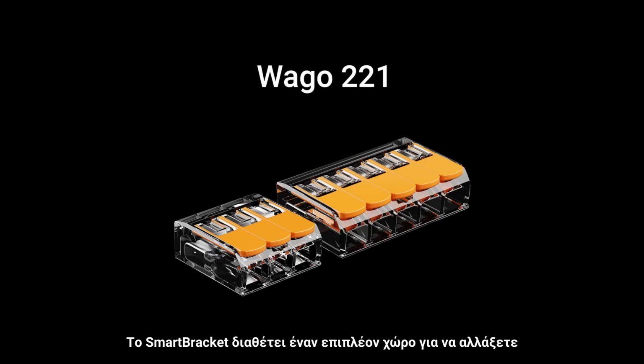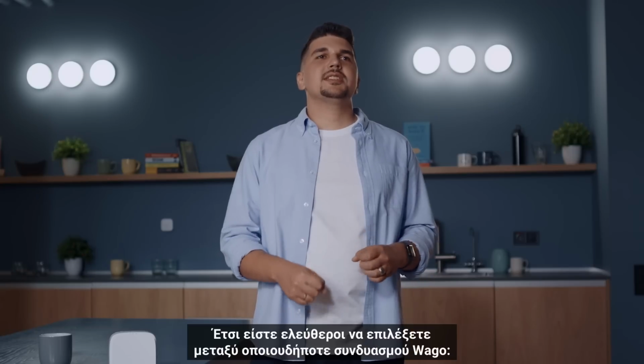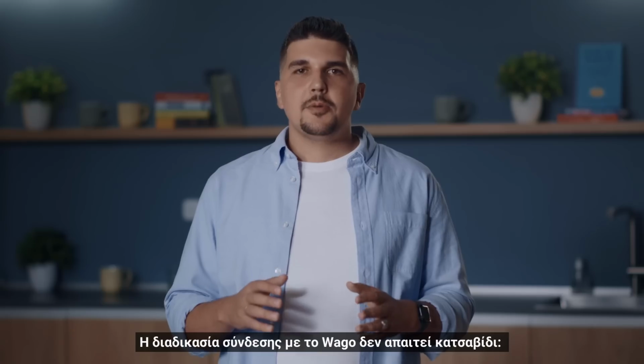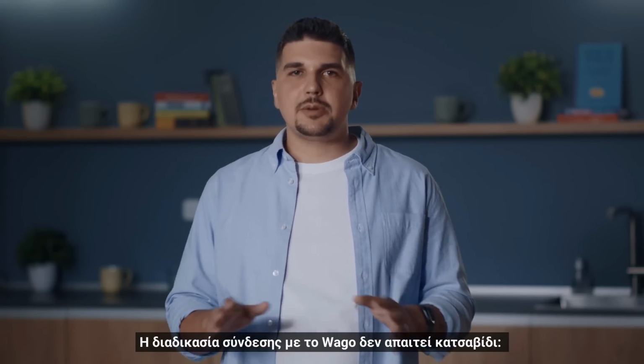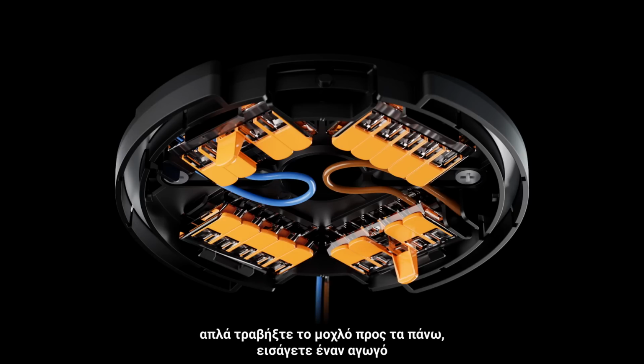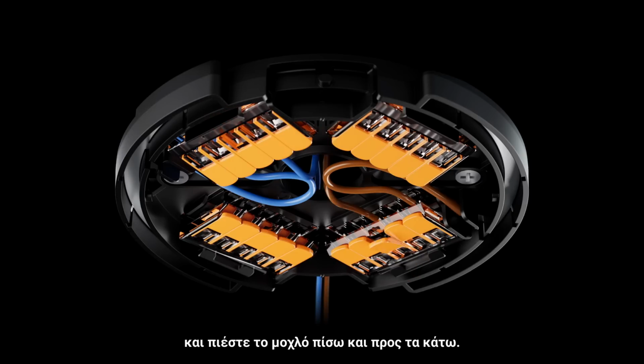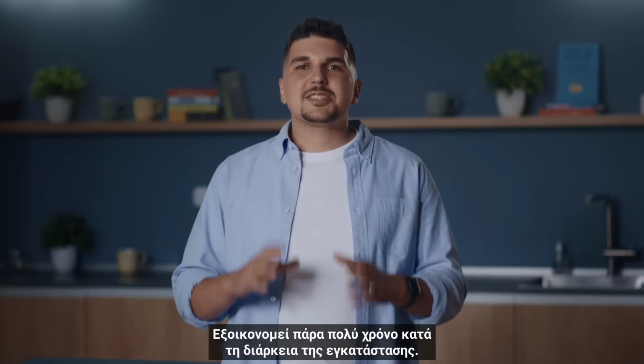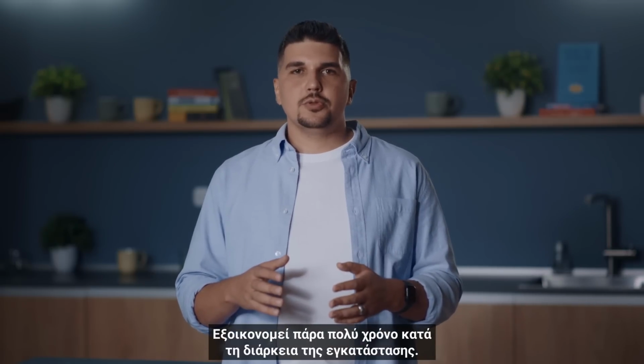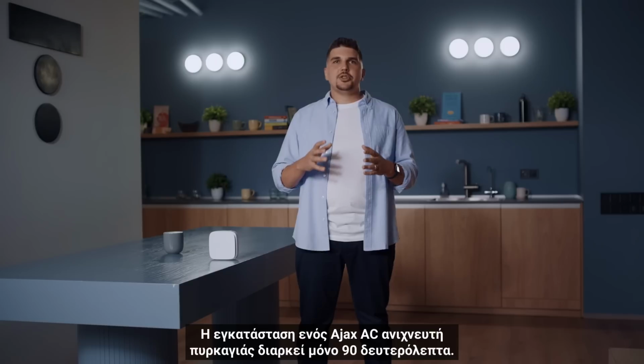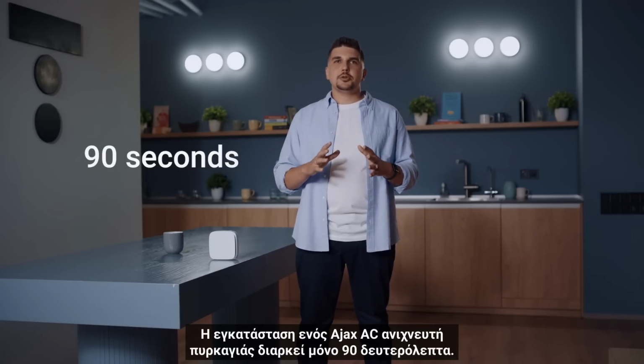Smart Bracket has extra space to swap terminals for bigger ones if necessary, so you're free to choose between any combination of WAGO. The connection process with WAGO does not require a screwdriver — just pull the lever up, insert a conductor, and push the lever back down. It saves a ton of time during installation. Installation of one Ajax AC fire detector takes only 90 seconds.